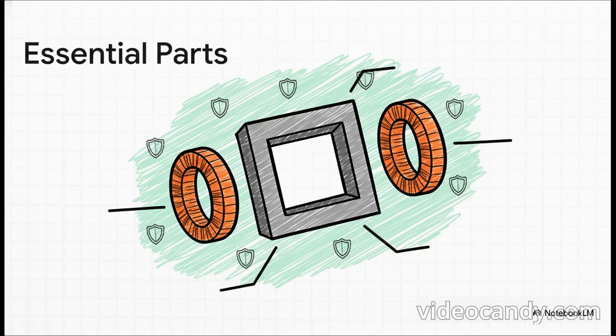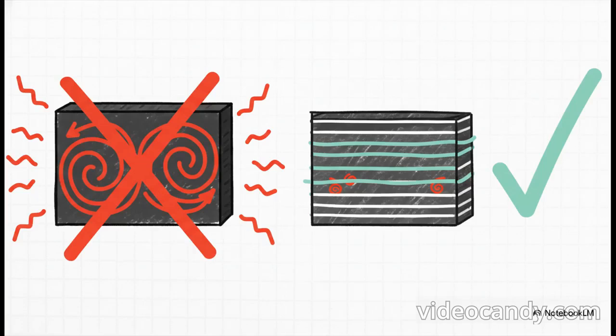Let's break them down. So, the core. Think of it as that magnetic superhighway. It's made from a special kind of steel, but here's the clever bit: it's not one solid chunk. Instead, it's built from thin, insulated layers stacked together. That design is genius because it stops wasteful little energy whirlpools called eddy currents from forming. Without those layers, a solid core would just get super hot and waste a ton of power.